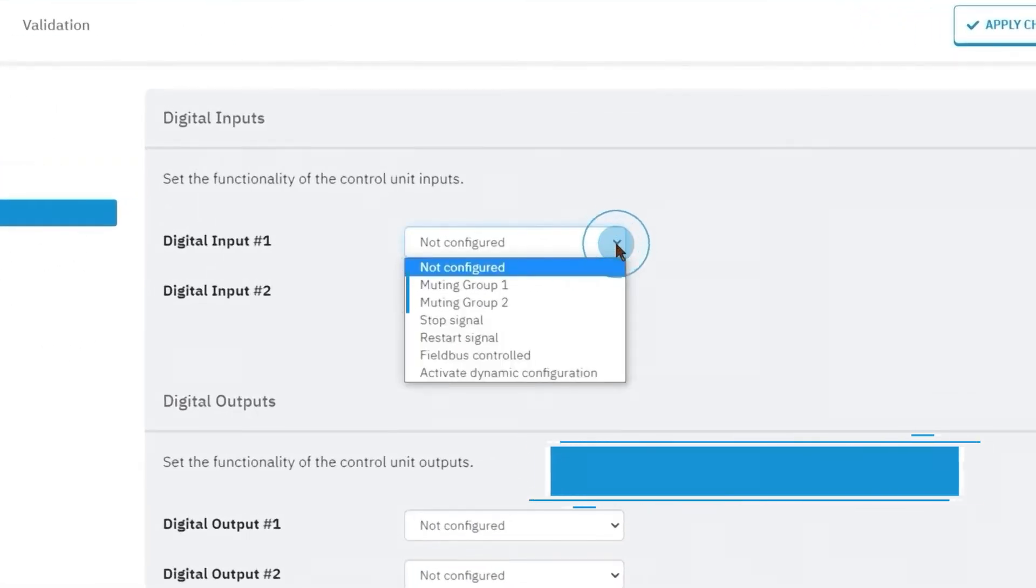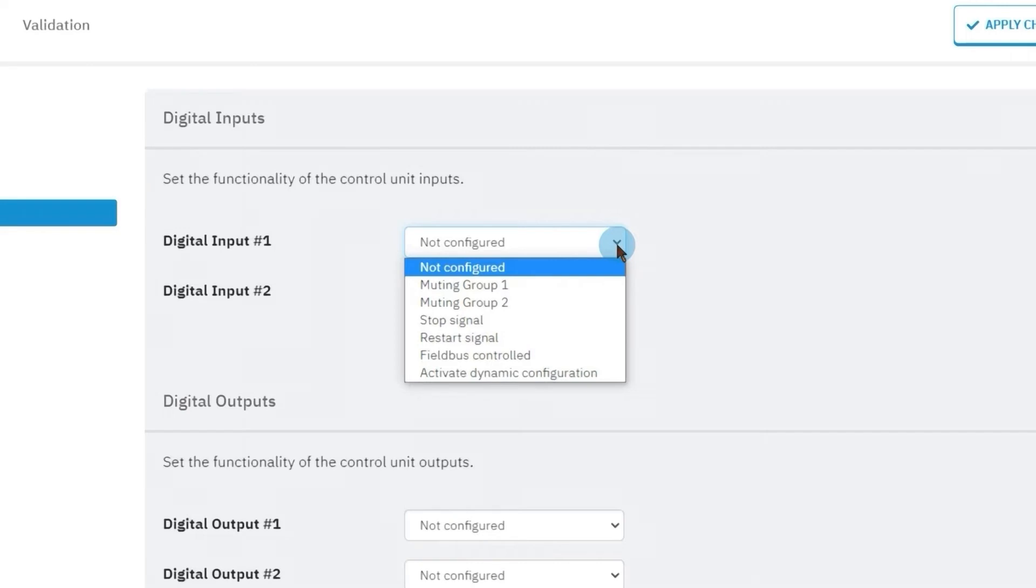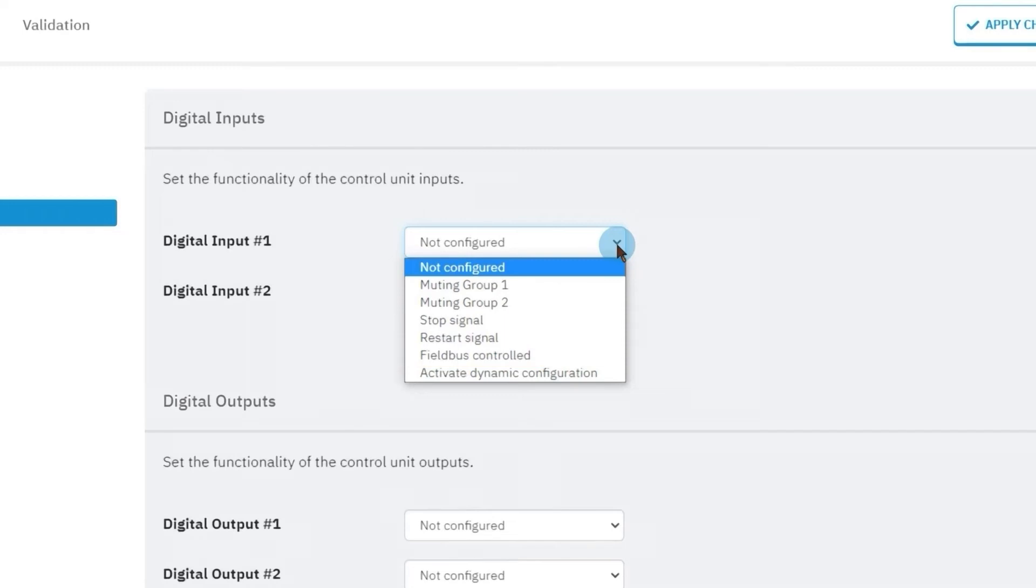The muting and restart signals. The stop signal, which means that the input is configured to be connected to an emergency button, forcing the deactivation of all the safety outputs. The field bus controlled input allows monitoring the input status via field bus, and the activate dynamic configuration allows switching configurations dynamically.